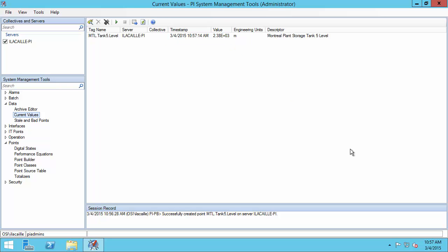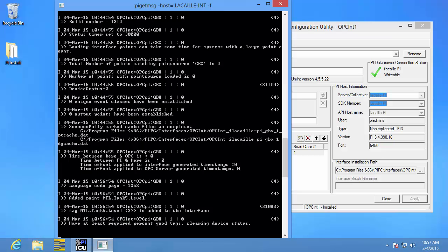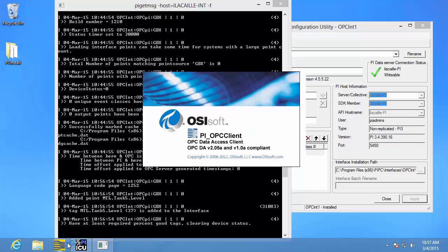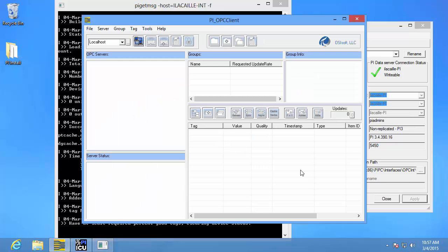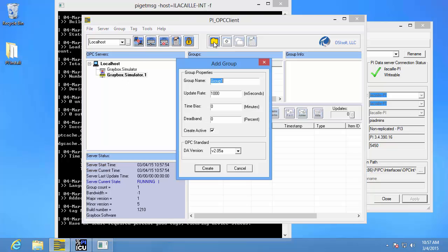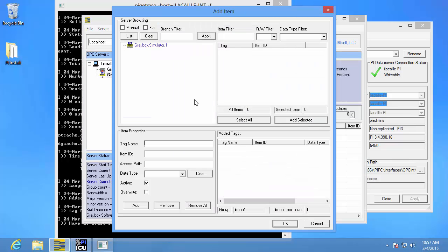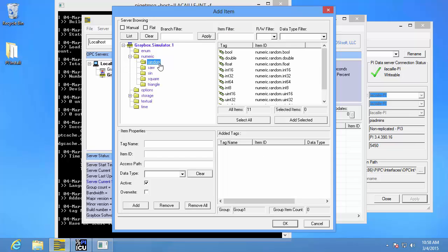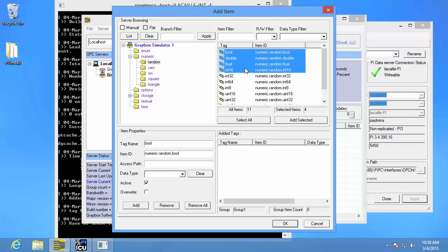Now I'm going to quickly show you the second way to create PI points — creating them in bulk using the PI OPC client tool. Let's go back to our PI interface node and start up the PI OPC client tool. We'll connect to our OPC server, create a group, and browse our OPC server. This time we're going to select as many items as we want to create on our PI Data Archive. You can select up to 500 items per group and up to 20 groups.